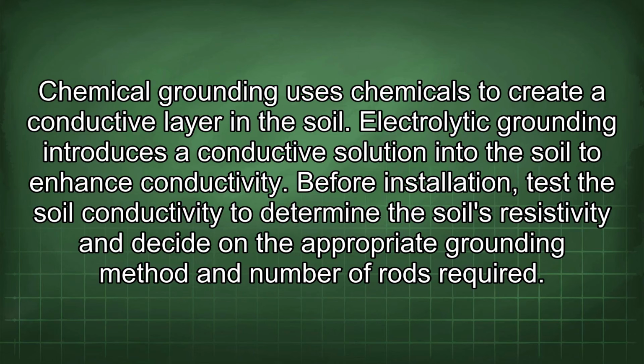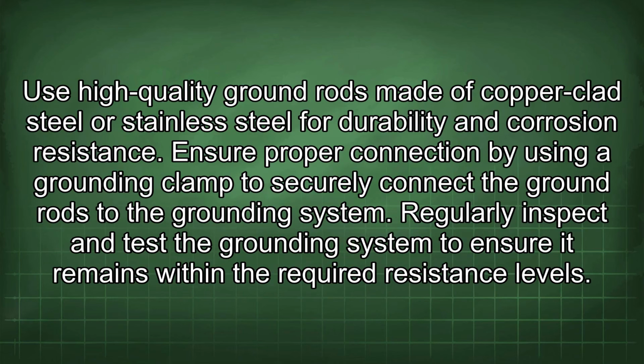Before installation, test the soil conductivity to determine the soil's resistivity and decide on the appropriate grounding method and number of rods required. Use high-quality ground rods made of copper-clad steel or stainless steel for durability and corrosion resistance. Ensure proper connection by using a grounding clamp to securely connect the ground rods to the grounding system.